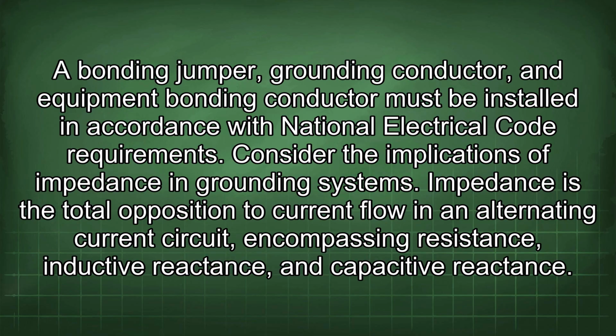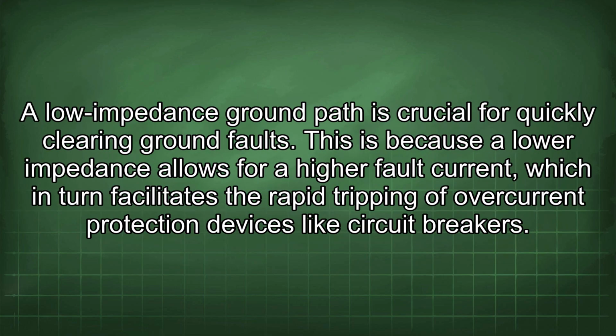Consider the implications of impedance in grounding systems. Impedance is the total opposition to current flow in an alternating current circuit, encompassing resistance, inductive reactance, and capacitive reactance. A low impedance ground path is crucial for quickly clearing ground faults. This is because a lower impedance allows for a high fault current, which in turn facilitates the rapid tripping of overcurrent protection devices like circuit breakers.